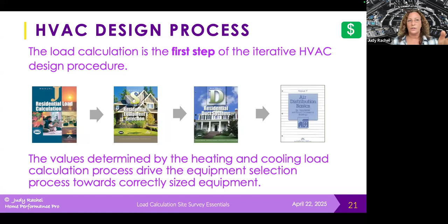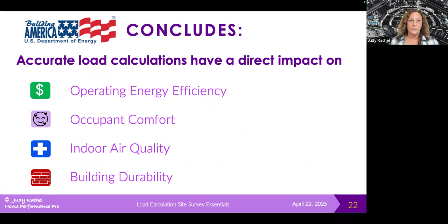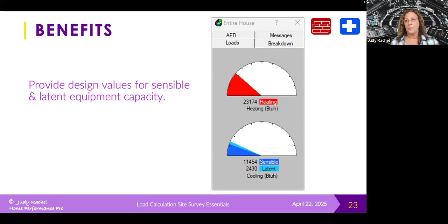And a load calculation has a direct impact on the actual operating energy efficiency of the system that ends up being installed. It also has a direct impact on our occupants' comfort, on indoor air quality, and on the building durability. We get both the sensible and latent equipment capacity when we do our load calculation, so that we can match that with equipment. Latent load is moisture in the air, and sensible is the temperature that we feel.